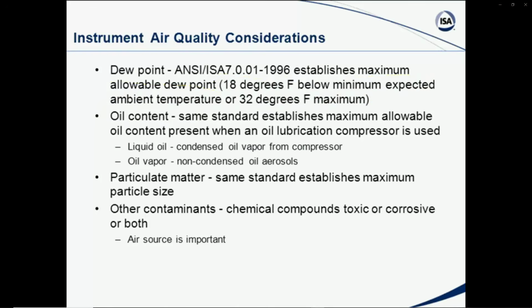Also, in this same specification, or same standard, the oil content is limited. You want to make sure that you don't have a lot of oil and oil vapor in this instrument air, because the quality considerations will not allow that as they operate with the flapper nozzles and the small movements of tubing and all. So you've got to be sure that you have that limited. Whereas normally you might have a plant air system, say at 100 psi distribution, and it may have oil in it because it's going to be used for jackhammers or other types of pneumatic equipment, and that's okay.